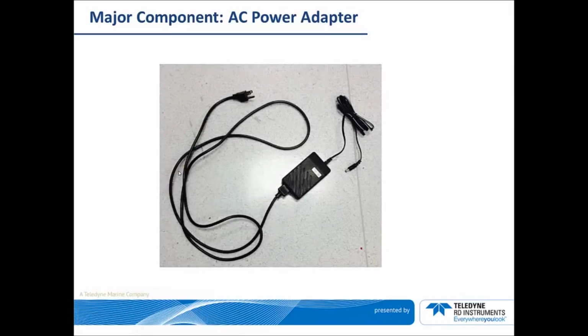The next major component is the RDI provided power supply or power cable. If the Sentinel V is configured with the optional end cap connector, then external power can be used. The optional AC power adapter provides 18 volts DC, with an input voltage of 100 to 240 volts AC. To conserve battery power, you may use the power cable when testing or experimenting with your Sentinel V in your lab. Again, the AC adapter provides 18 volts DC. If this input voltage is greater than the battery voltage, then the ADCP will draw all power from the AC adapter, even if the battery is installed and connected.